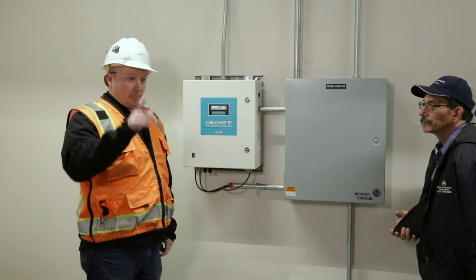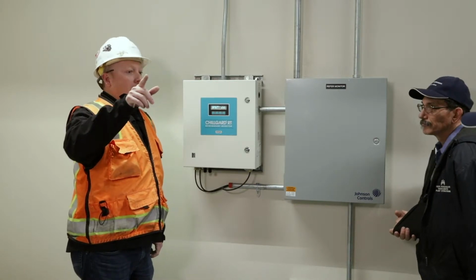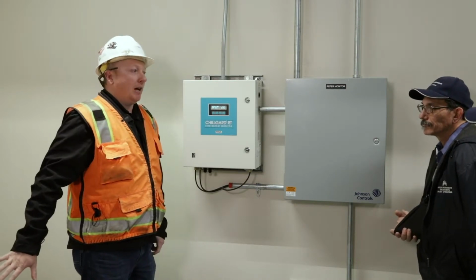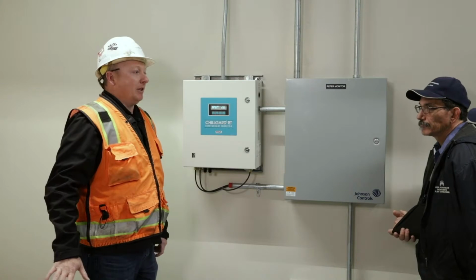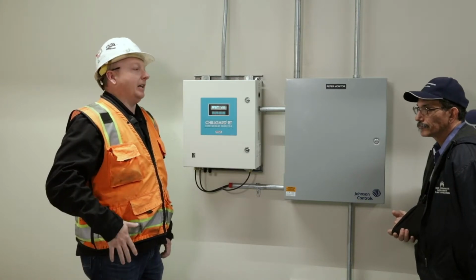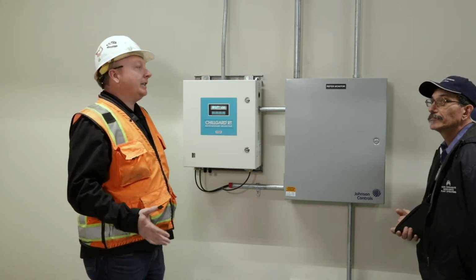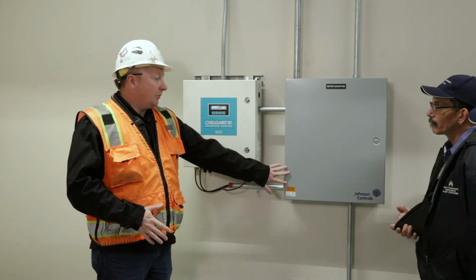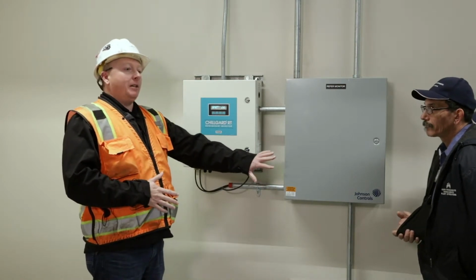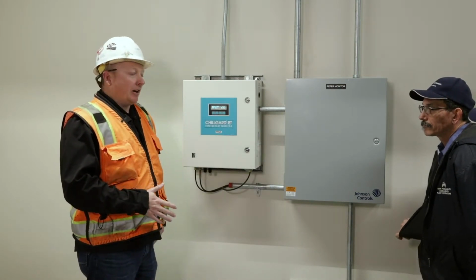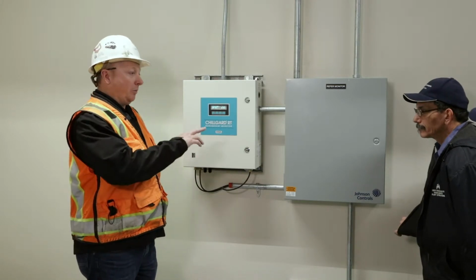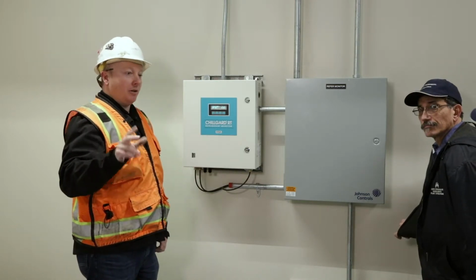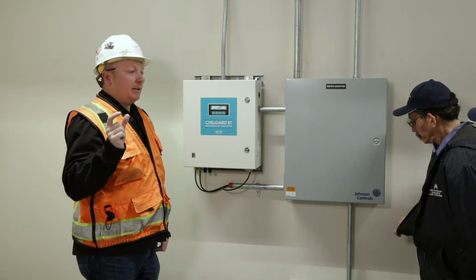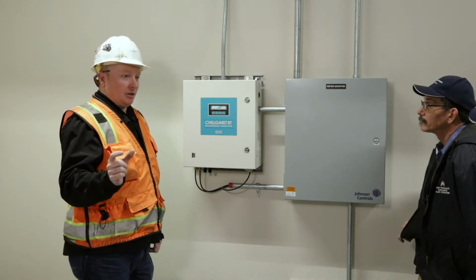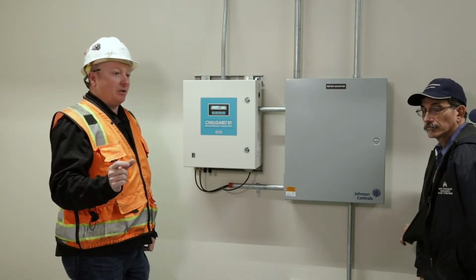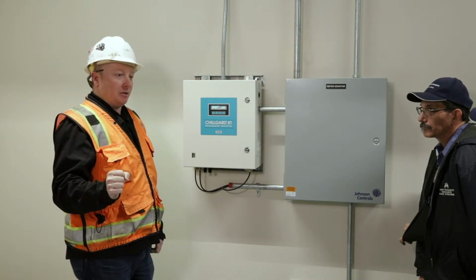It'll start the purge exhaust fan over there, and it'll alarm you down on the BMS that we have a leak detection alarm up here and everything is off. Inside this panel, we have a bunch of relays. The shutdowns for the chillers are actually hardwired. So we are on the York chiller, there's a contact for shutdown that we're actually hooked up to. So if it sees that contact closure, it goes into a safety shutdown.